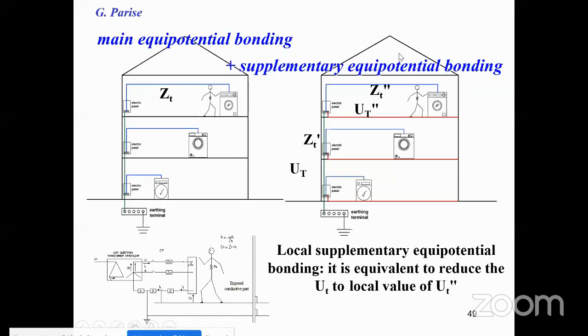When we use supplementary equipotential bond, you can see the local panel, the connection to the main ground conductor, the metallic element on the floor, and other extraneous conductive parts are locally connected to the ground.